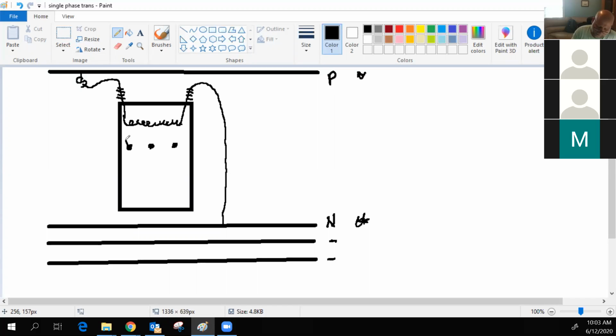All right, now the secondary side. We've got a winding that comes off this side in this direction, and we've got a winding that comes off this side in this direction, okay? Everybody knows the middle, what will we do with this middle bushing right here on the secondary side? That's the neutral, to the ground. Neutral, ground, yep, it all ties together. We'll tie it right here on this bus work, okay? And also, just like on the transformer on the field, this one, the tank ground is also grounded as well, okay?